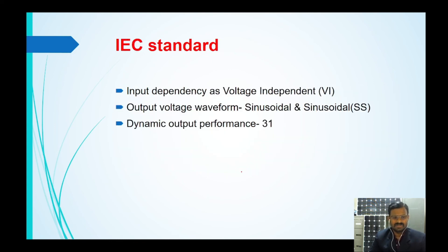The IEC standards for this type of UPS is given like this. It is voltage independent - irrespective of the input voltage variation, the output voltage can be kept constant with the help of a tap changing transformer. The second parameter, output waveform, is going to be sinusoidal for both cases, either in utility power mode or stored energy mode.